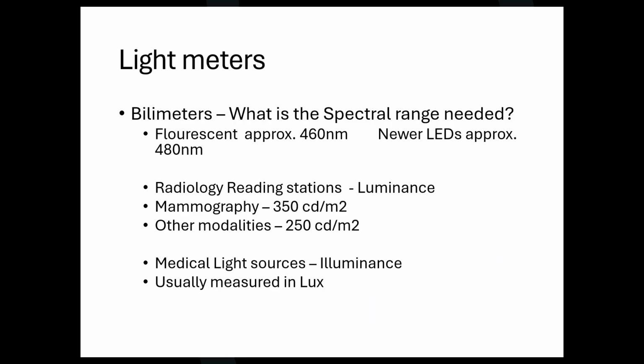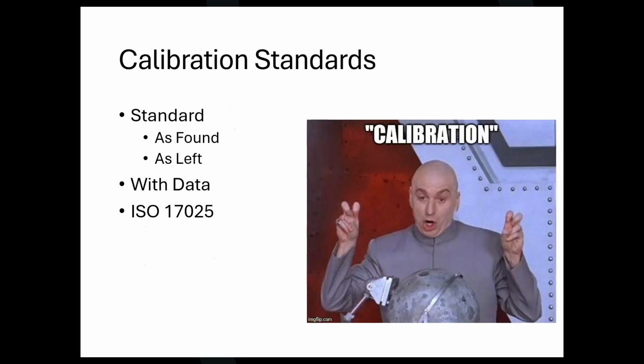I said, do your lights run at that 400 and some nanometer spectrum? Huh? This guy was coming in and doing that, and even what reading he was getting was only about 2% of range. Feel free to question your calibration people when they come in about what they're doing. Not all are created equal. But anyhow, you've got to have the correct device. You're measuring radiance, luminance, and illuminance. You've got to have the correct device, or you're going to have the wrong reading on it. All right, let's talk about calibration standards here a little bit.